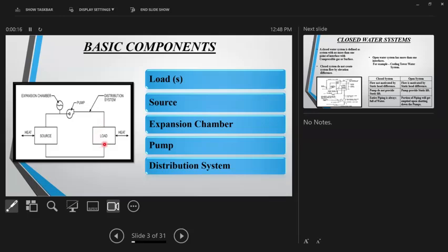So the basic components, four or five components of any chill water system, or for that matter any hot water system, are basically: a load, which could be a cooling load or a heating load; a source, which could be a heat pump, a boiler, or a chiller; one expansion chamber or expansion tank, open or closed, which allows for the expansion and contraction of water; and a pump and a distribution system, right? These are the basic components you will see in any chill water system. Today's intent is to see critical applications of a few of these. Of course, we are not going to talk about heat load calculations, that's a different thing. But about other important equipment and systems in the chill water system, we will try to go through each of them.